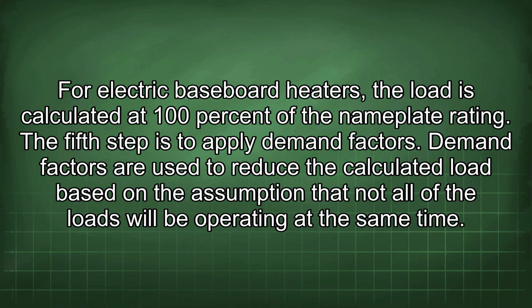The fifth step is to apply demand factors. Demand factors are used to reduce the calculated load based on the assumption that not all of the loads will be operating at the same time.